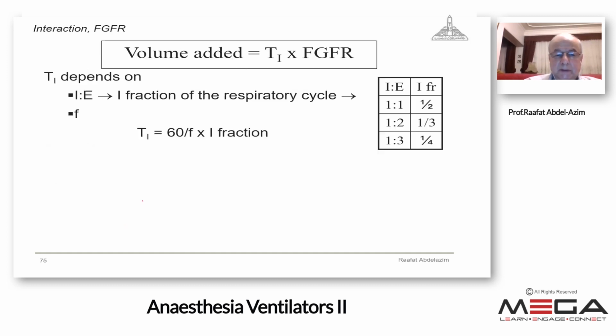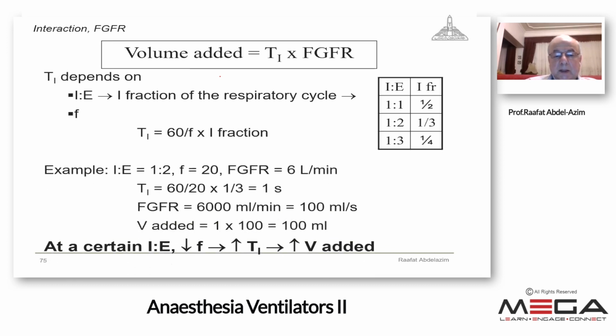How to calculate it? This is a fraction of inspiration to expiration. So the inspiratory fraction is, if the inspiratory to expiratory ratio is 1:1, this means that inspiration is half the respiratory cycle time. If it is 1:2, the inspiratory fraction is 1/3. And if it is 1:3, it is 1/4. The inspiratory fraction of the respiratory cycle depends on the time of inspiration relative to the total cycle time. We can obtain the cycle time by dividing 60 over the frequency, or the respiratory rate.